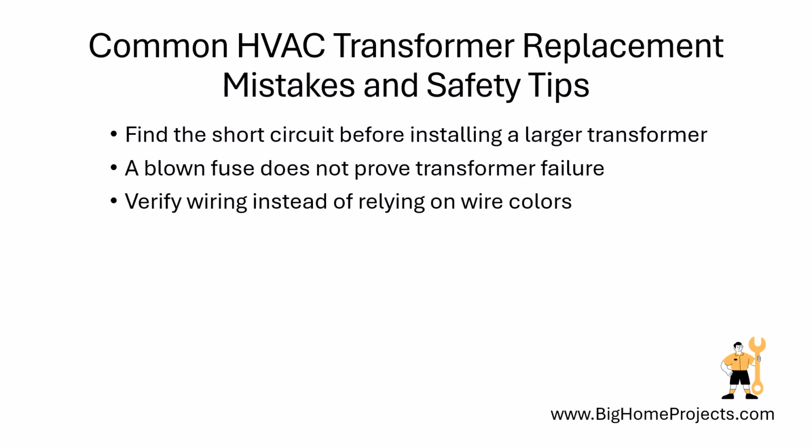A common mistake is installing a larger transformer without finding the short circuit, so the better step is to test every low voltage circuit before replacing it. Another misconception is that a blown fuse proves the transformer is bad, but the fuse may be protecting the transformer from a damaged wire or control component, so never bypass it with foil or a larger fuse.